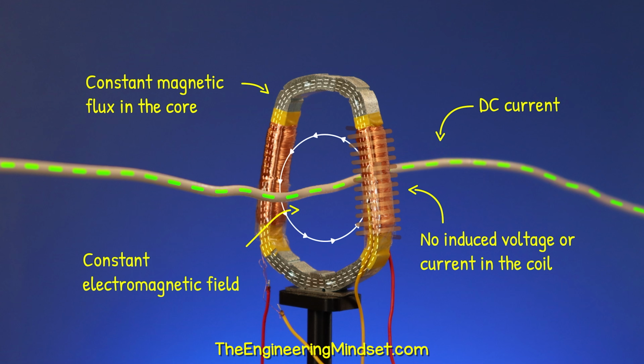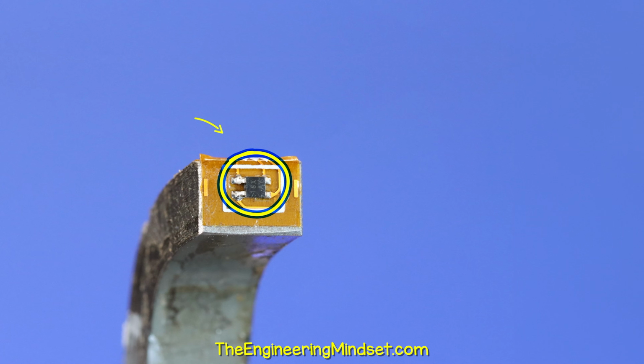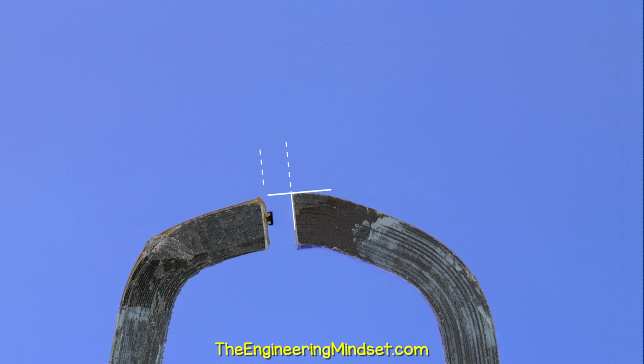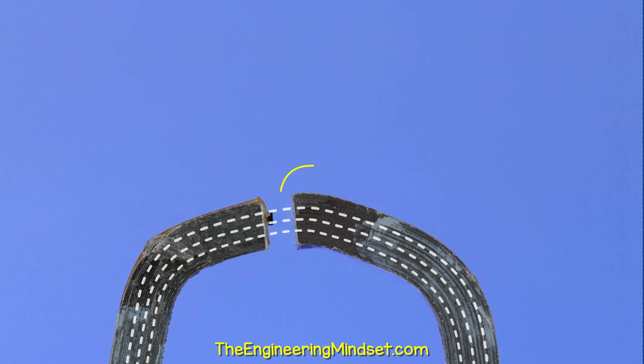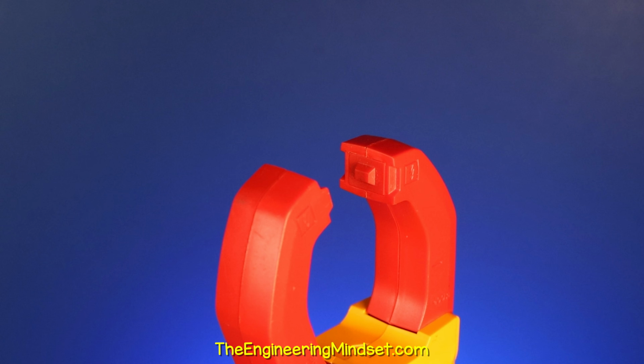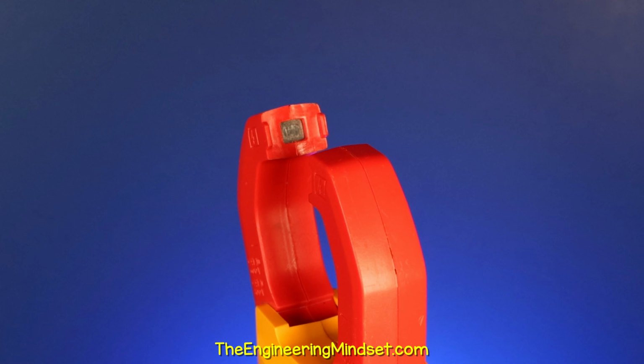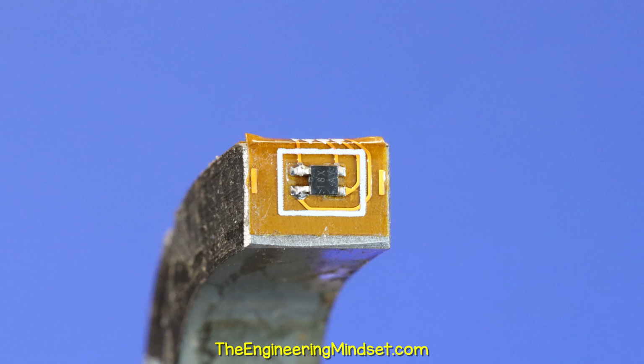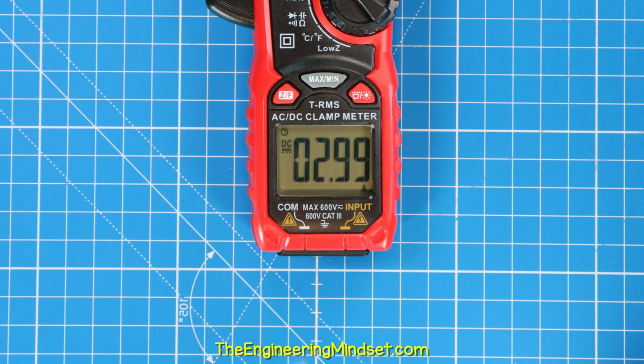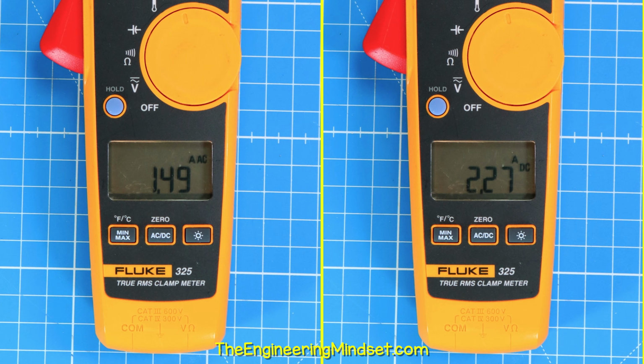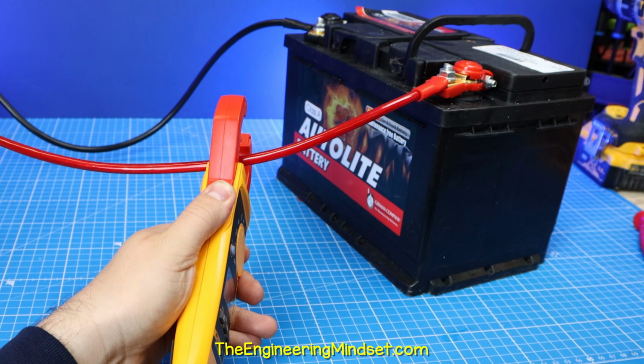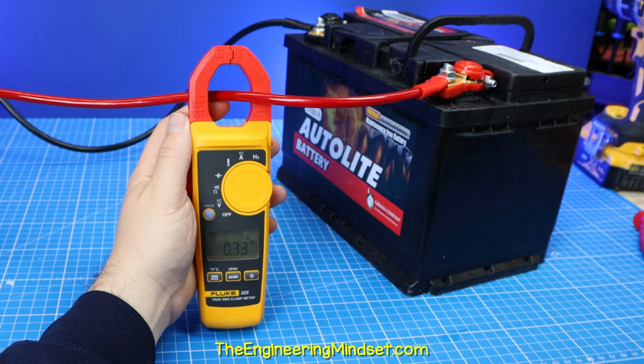The problem is that DC current is constant, so the coil can't detect this. Therefore, we have to use a Hall effect sensor instead of a coil of wire. There is a gap between the jaw tips which the magnetic field must jump across. That's why these meters only have exposed metal surfaces on one side, or none at all. The Hall effect sensor is placed in this gap. The magnetic field passes through this and causes it to produce a small voltage proportional to the current in the wire. The circuitry amplifies this and converts it into a current measurement, allowing us to measure both AC and DC current. So if you work with DC, make sure to buy a Hall effect meter.